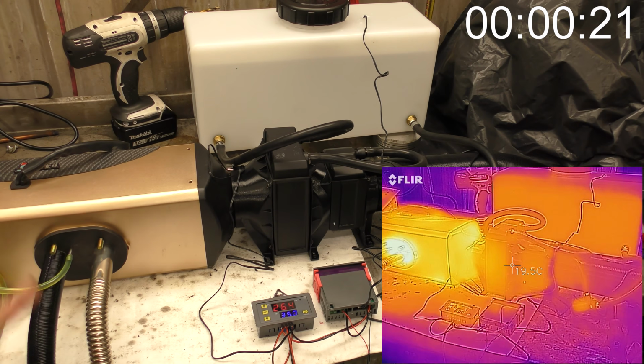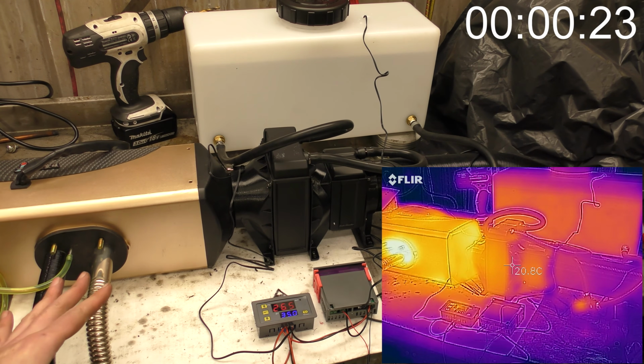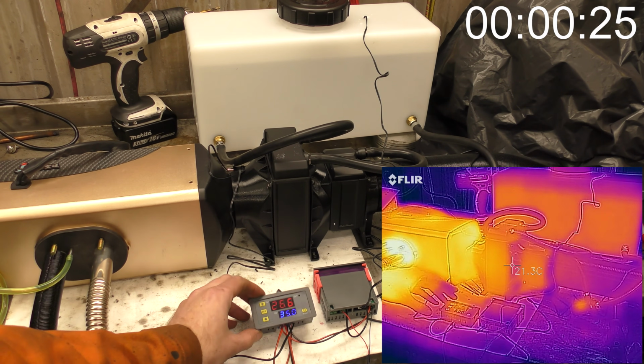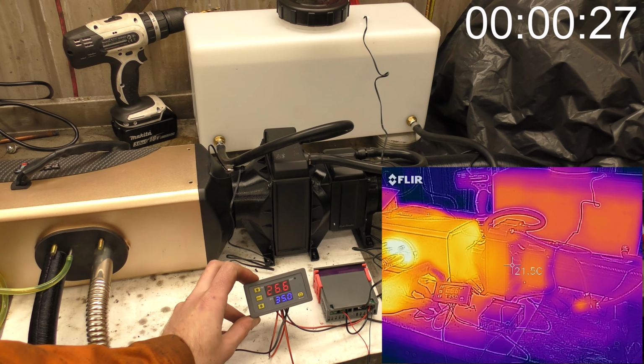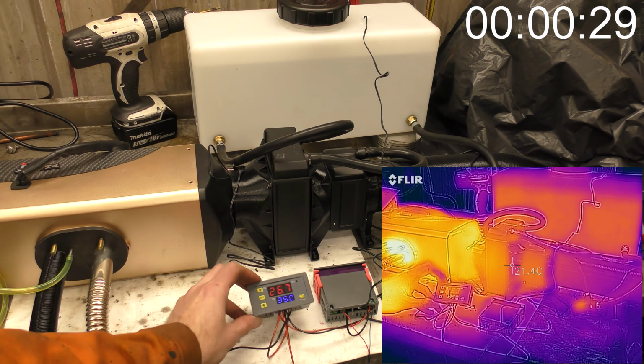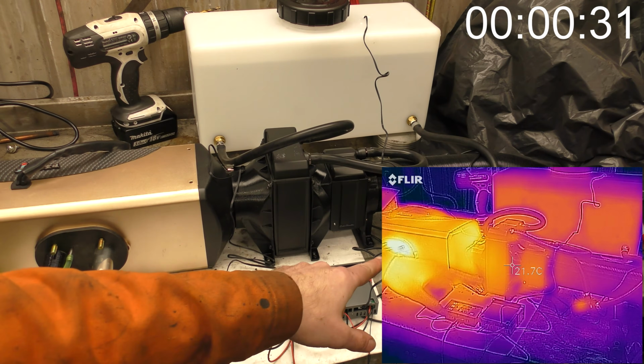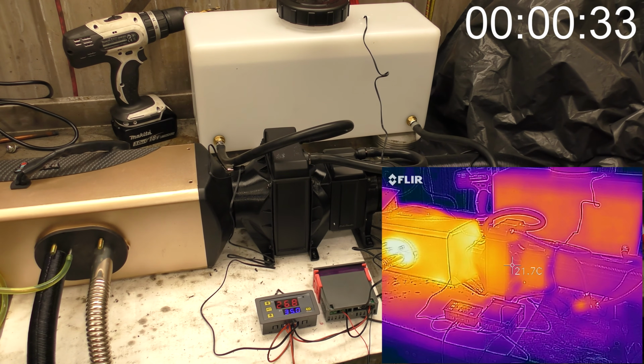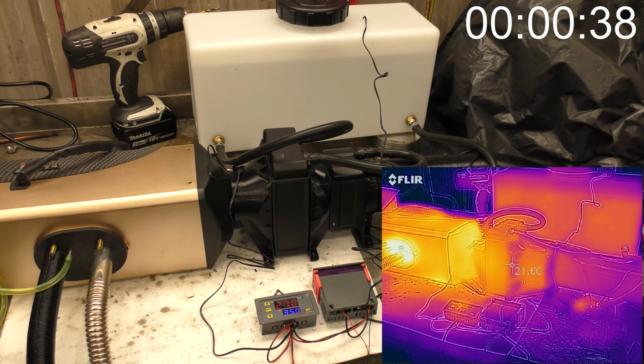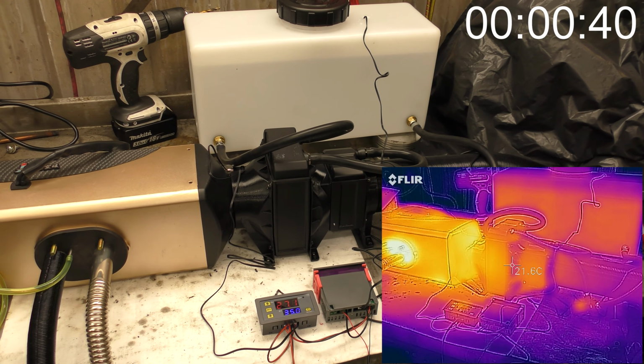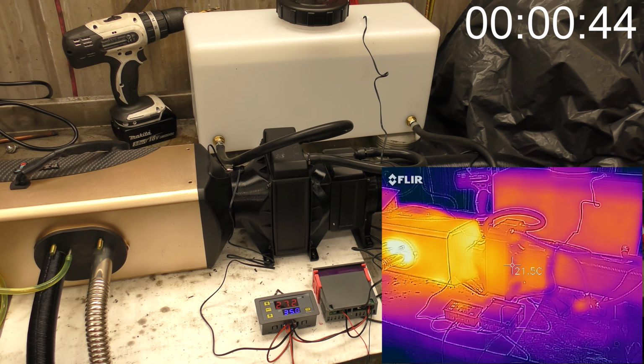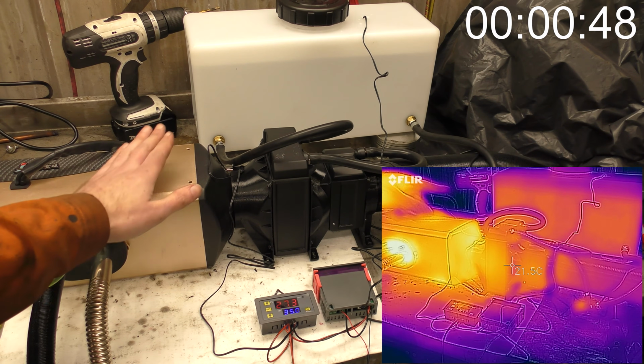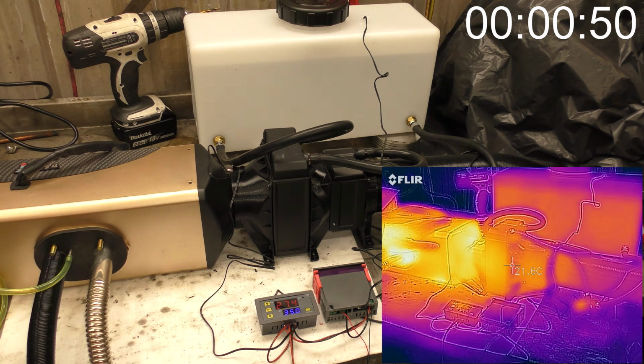So basically, we're just waiting for this to fire up, and then we'll hopefully get to see this click off from 26, it'll go up to 35, that'll turn on, and then the pump will turn on. So we'll just let it do its thing just now. With the FLIR, we'll be able to see the temperature at the inlet versus the temperature at the outlet once the pump has started circulating the water. We'll also get to see the tank temperature and see what we got up to.